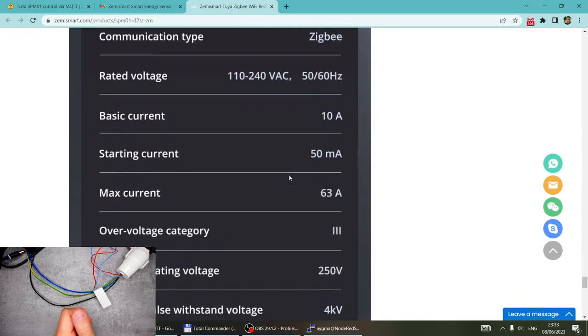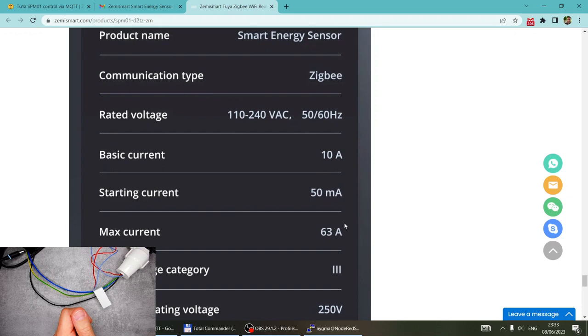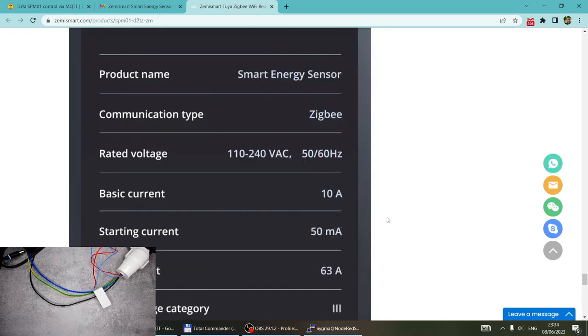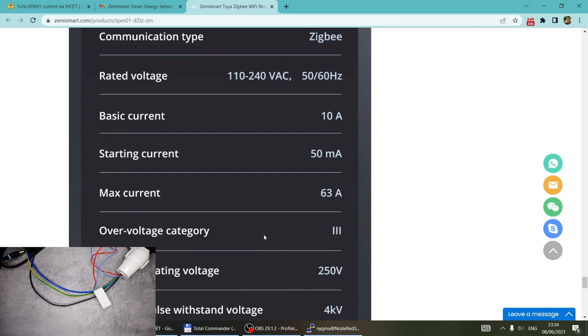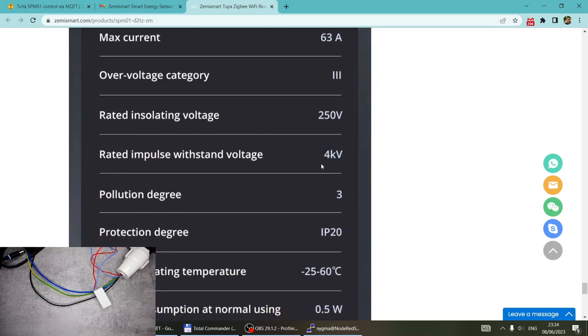You can see the dimensions here, and as I said, it goes all the way up to 63 amps, and the starting current is 50 milliamps. So 50 milliamps is like 5 watts at 110 and about 10 watts at 230, so that's the minimum it can measure. It's really designed to go behind or next to circuit breakers where you probably have a load of quite a few devices, so your consumption is likely to be more than that minimum value.